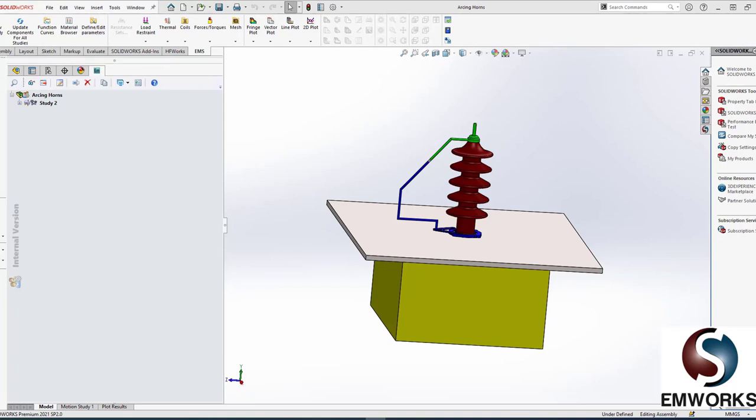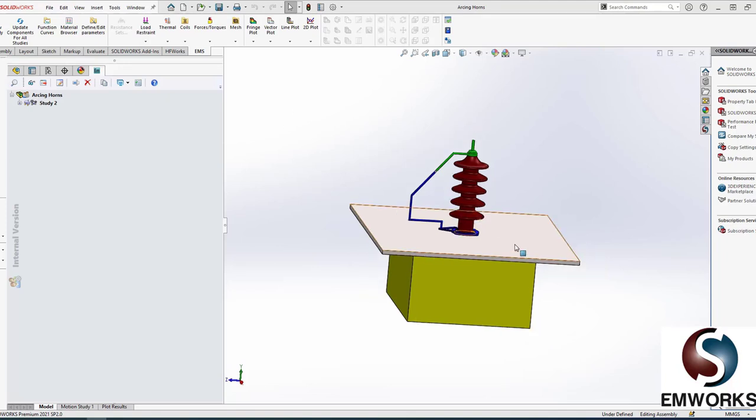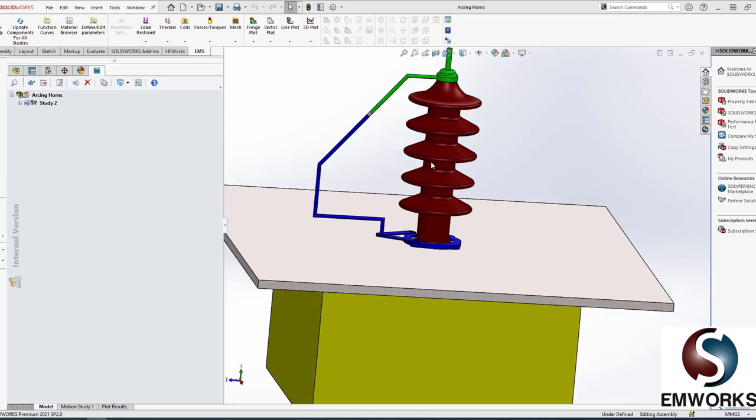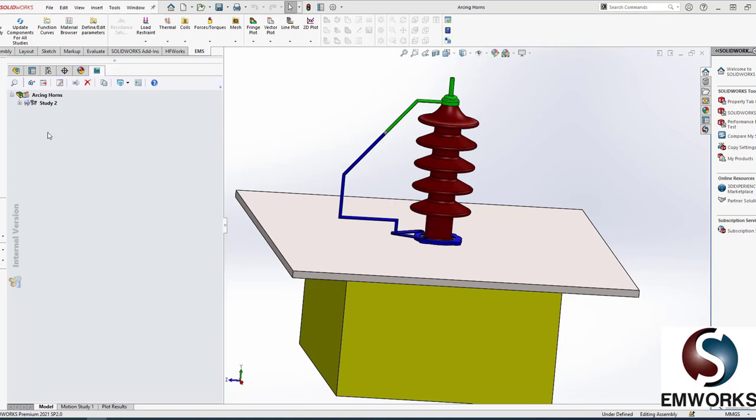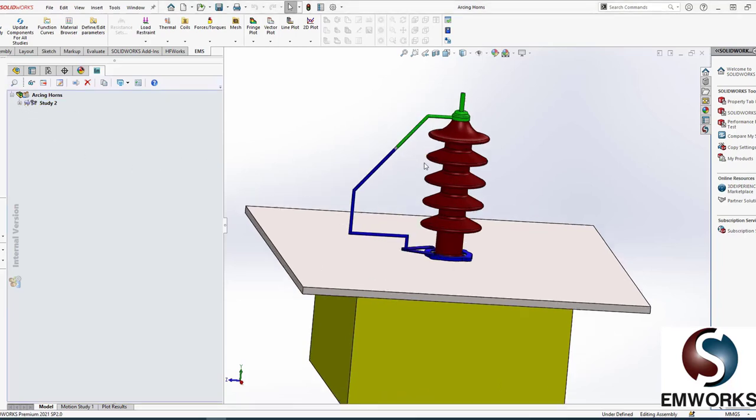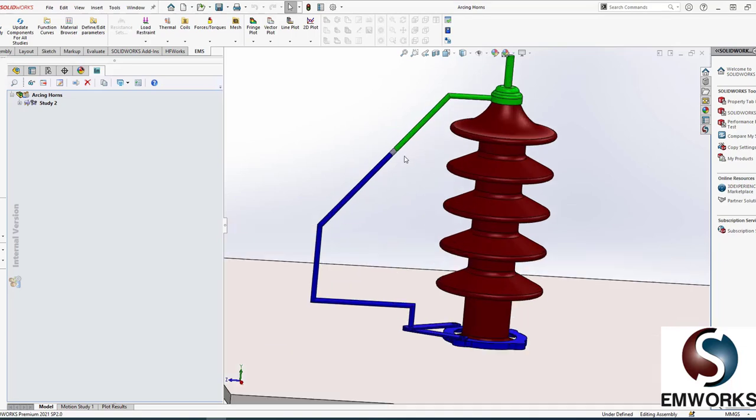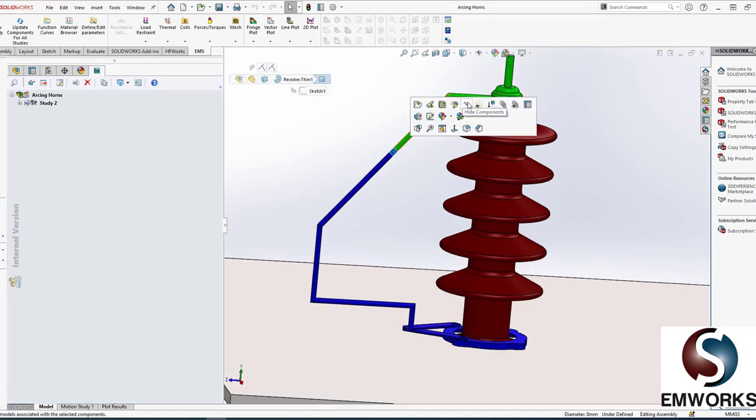Hi everyone, welcome back to EMWorks webinar series. My name is Ahmed Kebaier, and today's topic is how to optimize the air gap of an arcing horn in high voltage lines. As we all know, the idea of an arcing horn is to protect the valuable, expensive insulator in case there is a lightning strike, sudden load variation, or any other fault condition. So in brief the design, let me just hide this air gap.